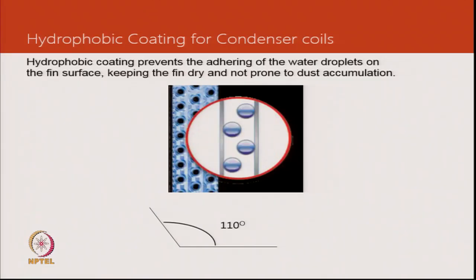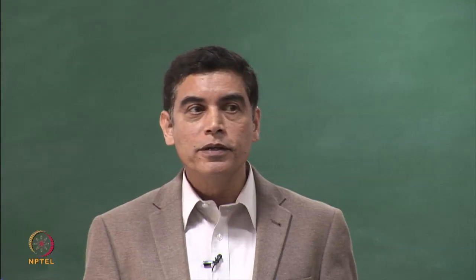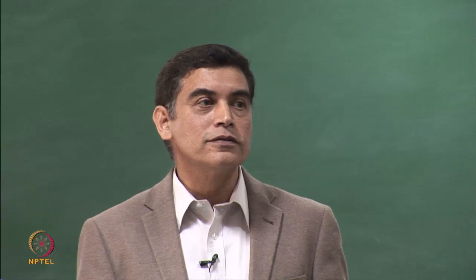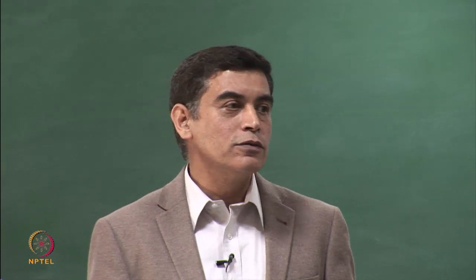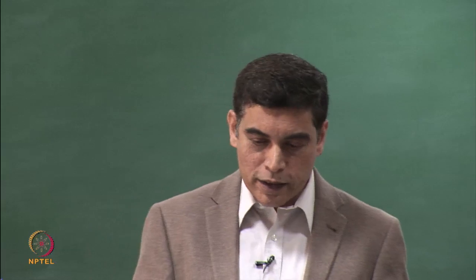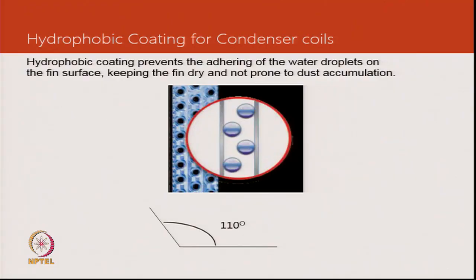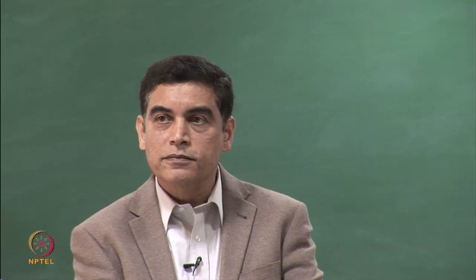Here the salt spray test demands are also much higher. So, if we were to test a coating, then we would anticipate it being good for more than 1000 hours of salt spray test, and that is because outside air is not so controlled. There is likely to be more corrosive gases. It is subjected to storms, dust, and all that. So, another claimed benefit of the coating is that the surface remains free of dust.